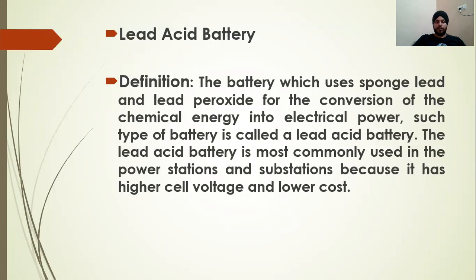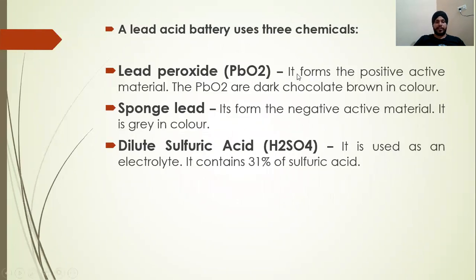The main chemicals are: first, lead peroxide (PbO2) for the positive plate, which is dark chocolate brown in color. Second, sponge lead for the negative plate, which is grey in color. Third, dilute sulfuric acid (H2SO4) as the electrolyte in a ratio of 60% water and 40% sulfuric acid. These chemicals react to produce electrical energy.